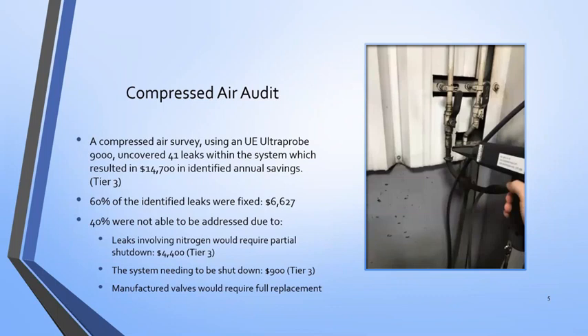Compressed air systems very frequently have air leaks — pinhole leaks in rubber hoses, hose clamps, valves, and such things. What I was able to do was take the UE Ultraprobe 9000, which uses ultrasonic detection, and identify the locations and size of these leaks throughout their system. I identified 41 different leaks with an estimated $14,700 in cost avoided.